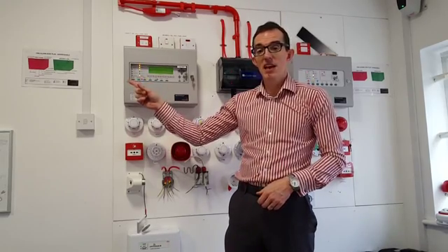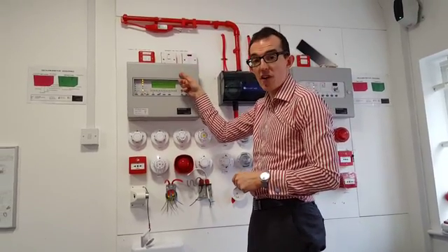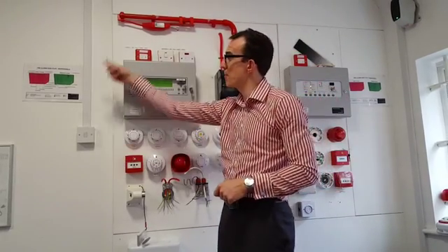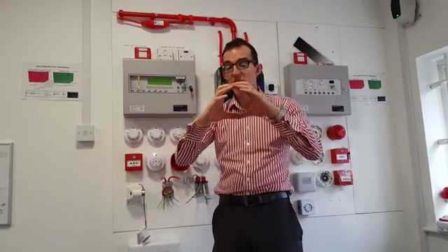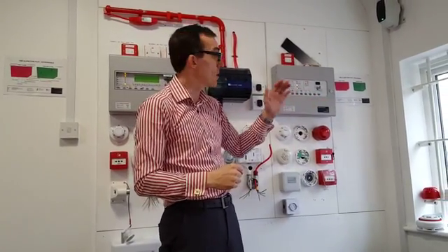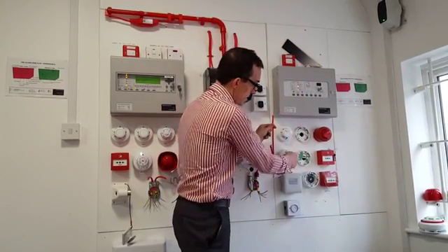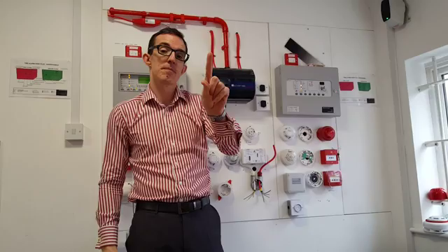And lastly, we're going to talk about L. So L, in the context of fire alarm systems, is for loop. So an analog addressable intelligent fire alarm system has a loop of cabling. So the cables start at one point on the fire alarm system, they go round the entire network of devices and they come back. So it's a continuous loop. Unlike a conventional system, which doesn't have a loop, it has radials or fingers. So on a conventional system, the cables leave the panel and they go out to all the devices and then they stop, just like a finger.